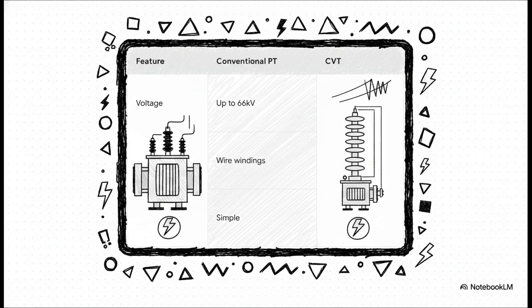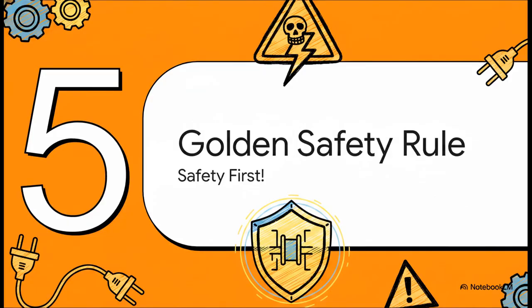So engineers invented the CVT, or capacitive voltage transformer. Instead of just relying on a magnetic core, it uses a string of capacitors to drastically drop the voltage before it even reaches the transformer section. It completely solves the massive size and expense problem, making the unit much leaner and cheaper. And here's a mind-blowing bonus. Those CVTs can actually carry high-frequency communication signals right over the power lines, which allows substations to talk to each other without needing any separate telephone wires. That's just brilliant. Which leads us to Section 5, the golden safety rule.